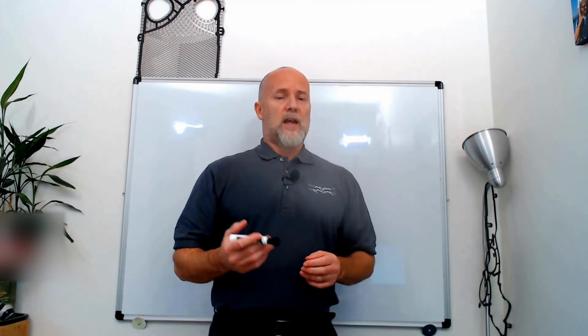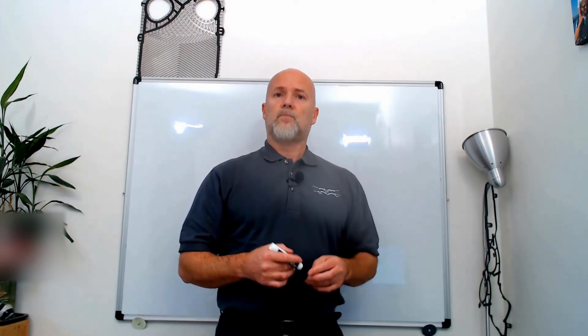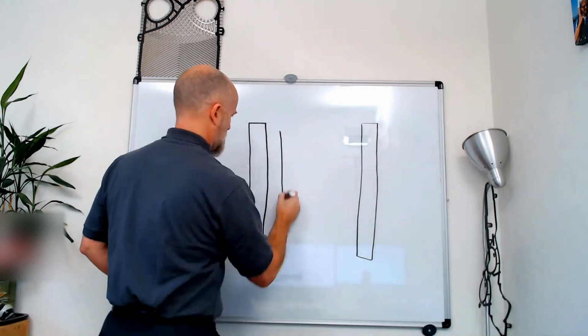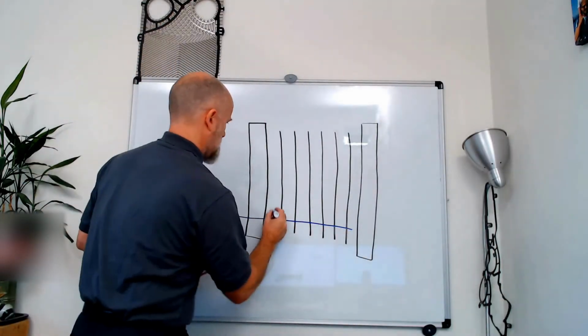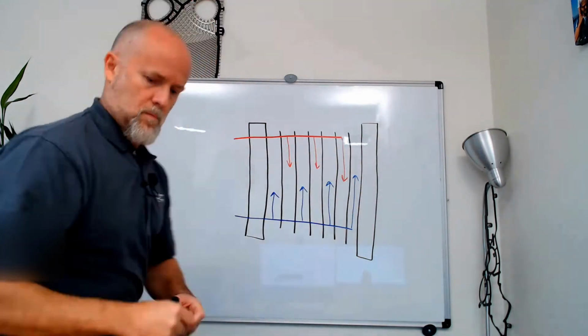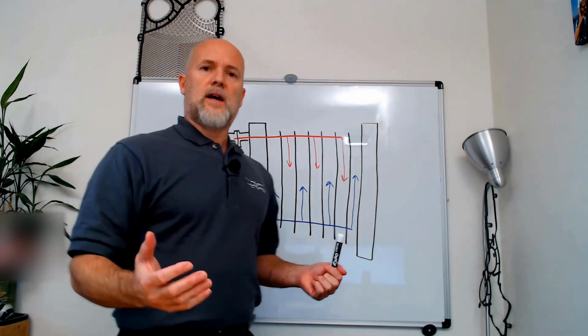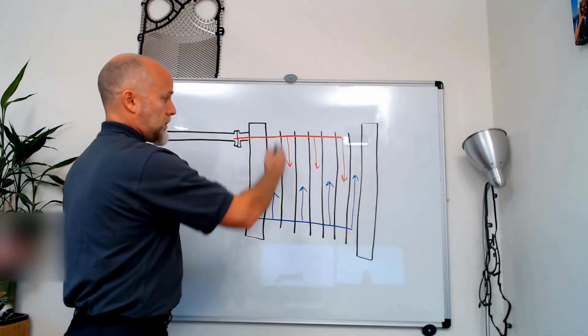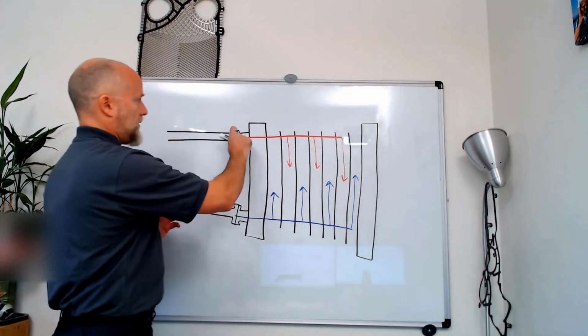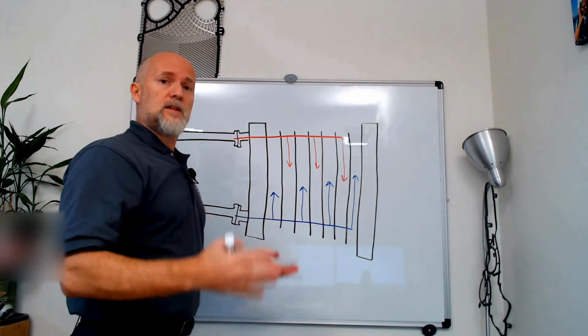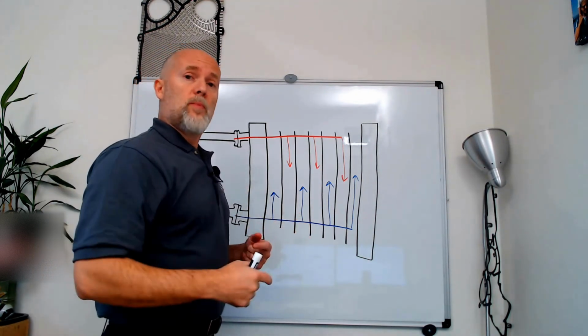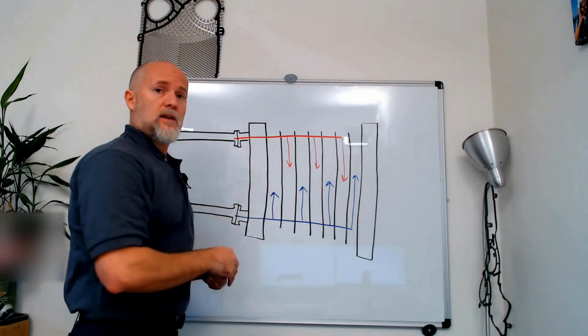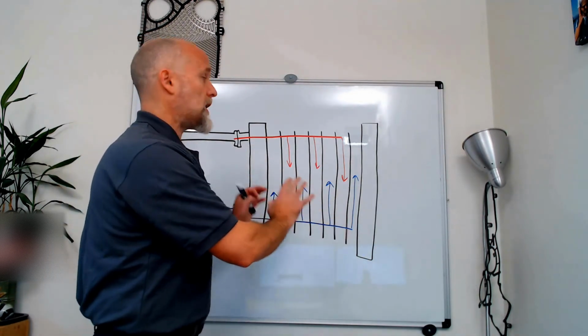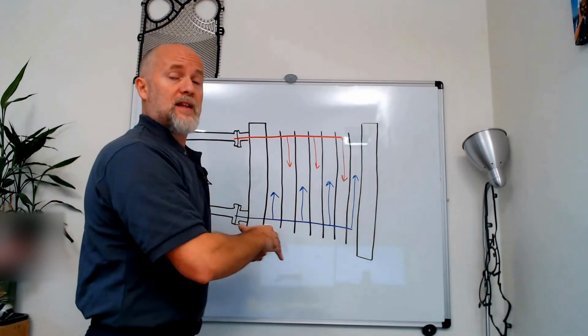A good alternative, if you have performance issues, is to run a cleaning in place or a CIP. So what exactly is a cleaning in place cycle? Let's have a look. So in a cleaning in place cycle, here you have your heat exchanger with the plates and the hot side and the cold side and the flanges and the piping. In a CIP cycle, you connect in a loop chemicals that clean the channels inside of the heat exchanger, so clean the plates without having to mechanically open and take the plates apart.